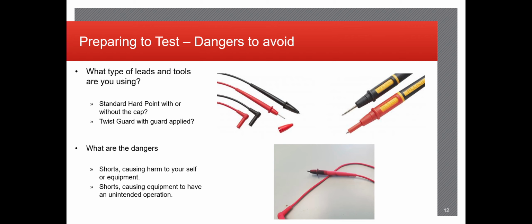What types of leads are you using? What you see here are two very safe options of test leads for your multimeter. You can see that the top two pictures are different models but have the same purpose. They expose the least amount of conductive metal on the lead as possible. This is really important because you want to avoid any possibility of arcing, meaning placing a lead on one terminal that has power to measure it and accidentally having another part of the lead hit something else, whether it's the cabinet or another terminal on the relay, which can be detrimental because that could damage the relay, and that wouldn't be good because those are expensive.